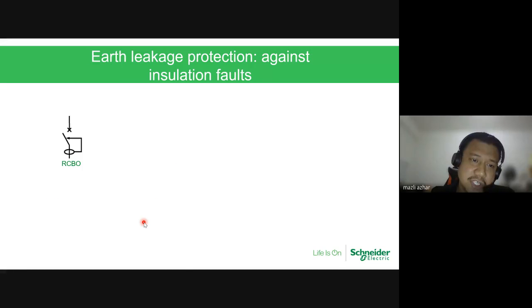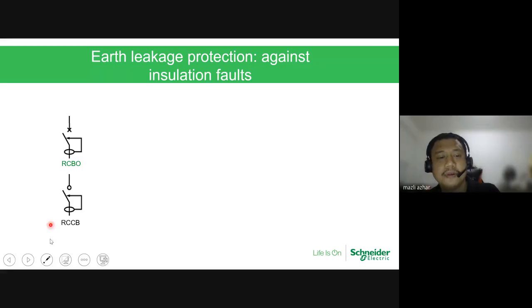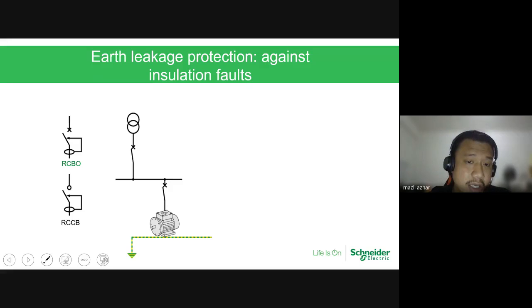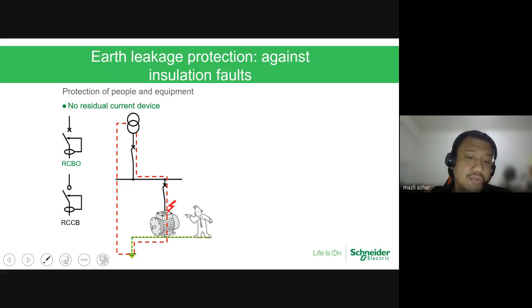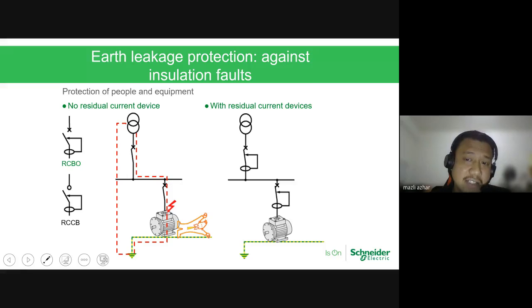So earth leakage protection, this is a terminology, a very simple example. So you have RCBO or RCCB. So you have a motor provided from the transformer, you have an isolator, but when there is a leakage, it will flow to the system. But when you have no residual current device, what will happen to you? If you accidentally touch it, you become an earth. Then you get electrocuted. With a residual current device, when there is a leakage, it will open up the circuit automatically and ensure the safety of the user if they are touching it. All right. So this is where it's very important.